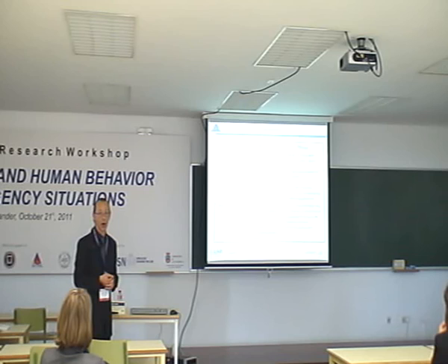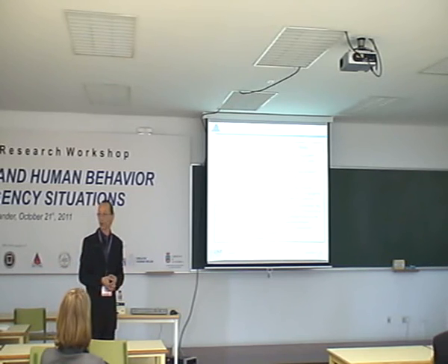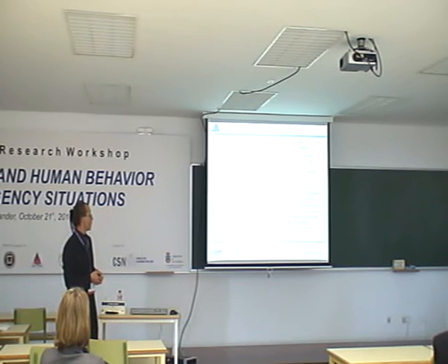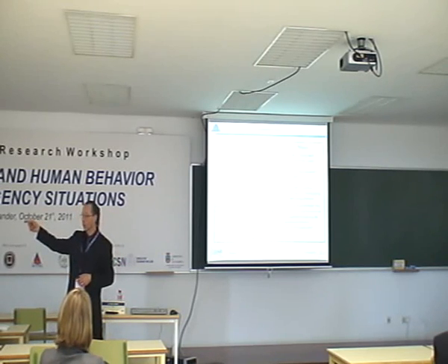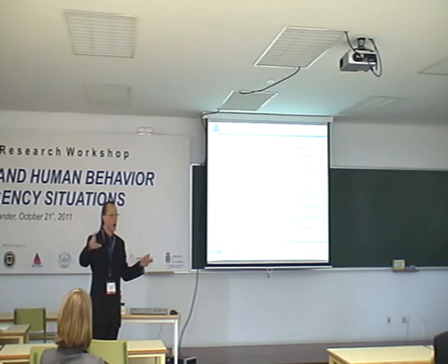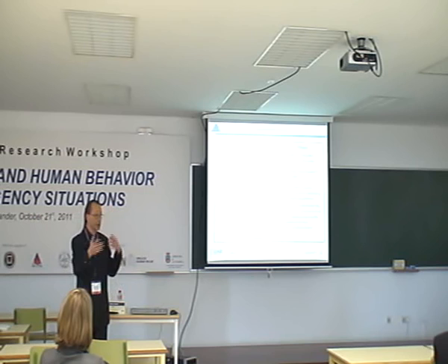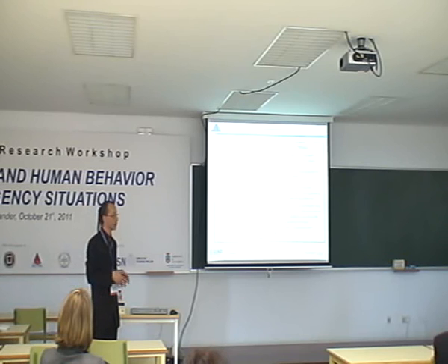of the computing power available right now, it's not possible to have a strong coupling between the models. When you are speaking about thousands of simulations, it's not possible to make thousands of CFD simulations for statistical analysis. So we're obliged to use a weak coupling, when we know for sure that people have an effect on the fire. I mean, if we go out here and open the door, of course it changes the ventilation of the room, and if there is a fire somewhere here, it will change its course because we are evacuating. So this can't be taken into account right now, but maybe in the future.